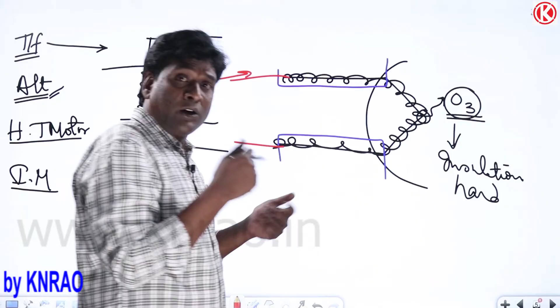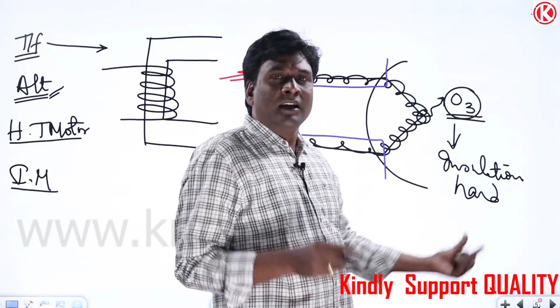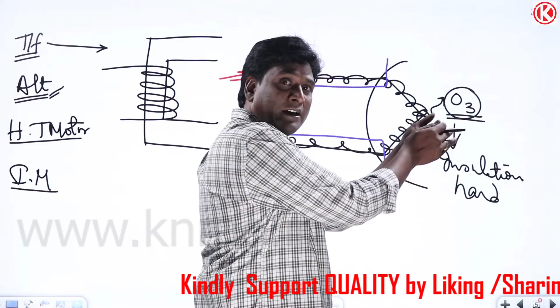Because of mechanical stress, back-to-back connection windings are going to have some vibration. Because of that vibration, insulation already became very hard, and it will break into small broken pieces. Now because of this mechanical stress, what will happen? It is going to give pitting of insulation, in the sense some small pieces will be dropped out.